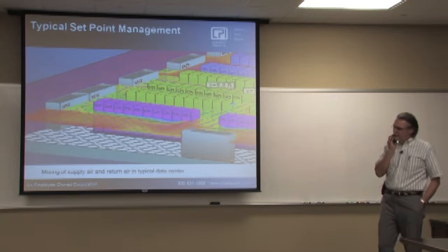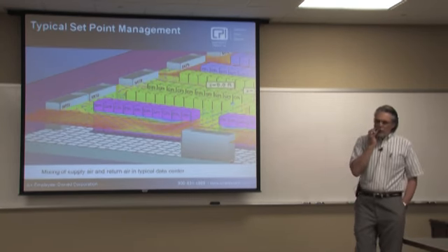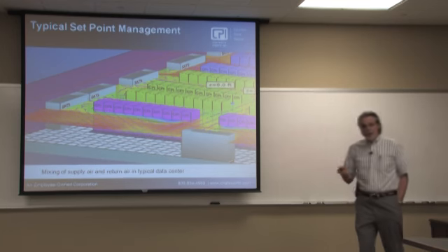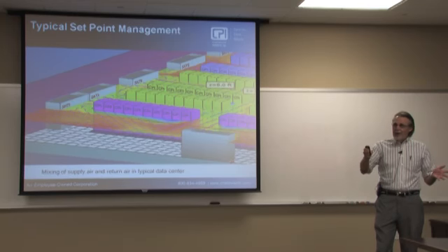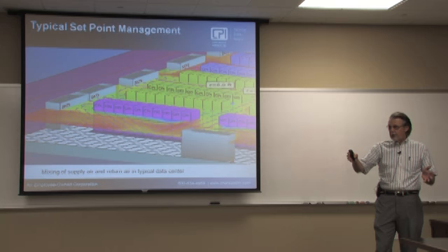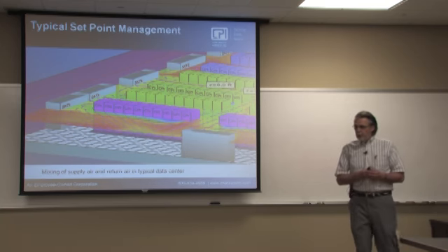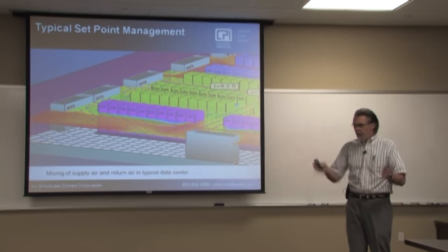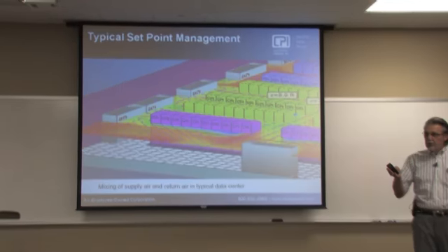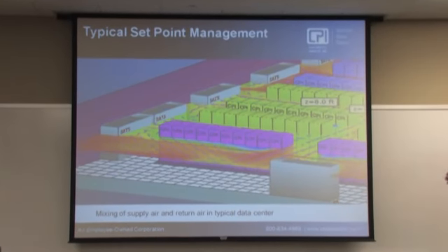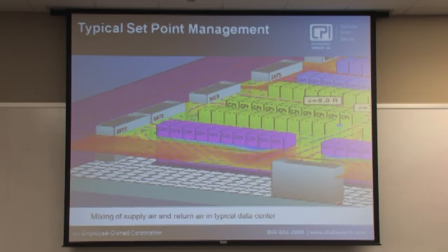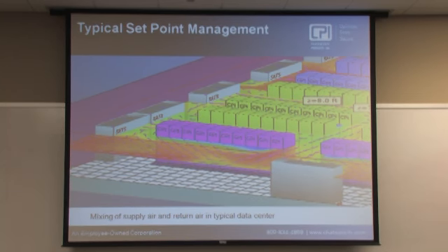So what drives that behavior? Because we've got a lot of air in that data center that's significantly higher than 72 degrees, and we can supply air to our computers higher than 72. So why do we want to start cooling at 72 and drop it from there? Well, because we got all this mix-up of hot and cold air in the data center.